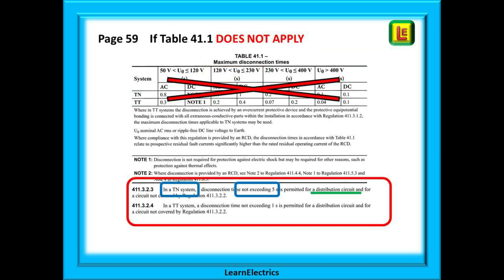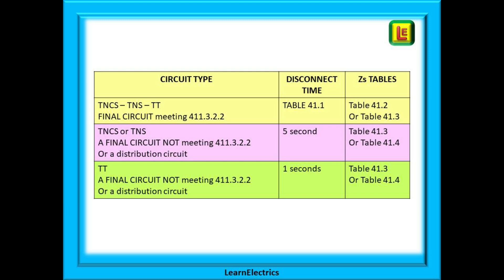If table 41.1 does not apply, what do we do? Just below the table are two important regulations that do pop up as exam questions. Regulation 411.3.2.3 tells us that if table 41.1 is not applicable, or if it is a distribution system, then for a TN system we allow a disconnection time of five seconds. Regulation 411.3.2.4 tells us that if table 41.1 is not applicable, or it is a distribution system for a TT system, then we allow a disconnection time of one second.